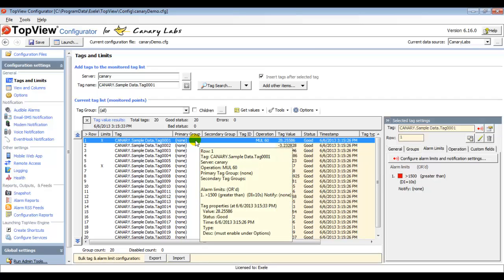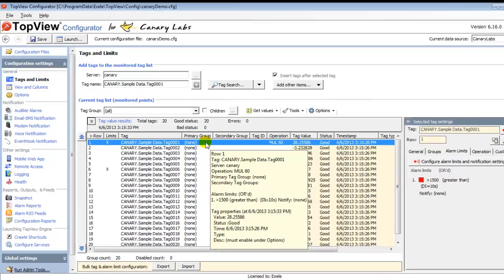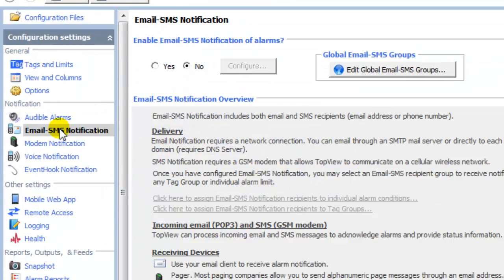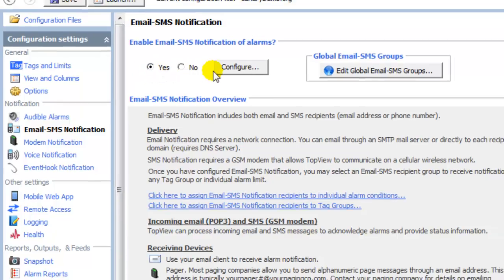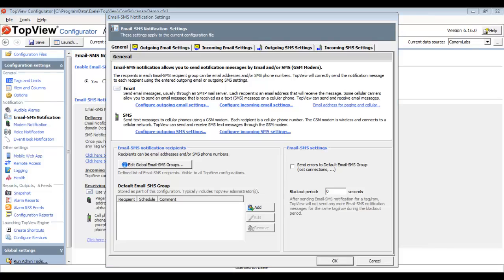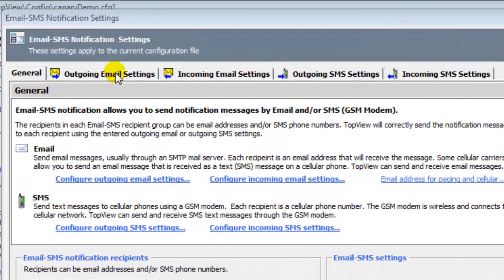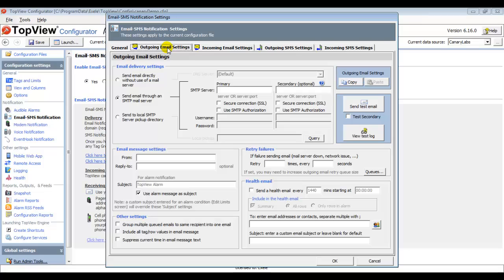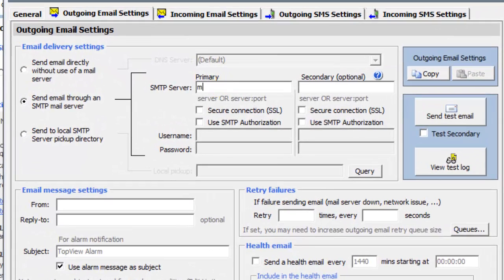I would like to send an email notification when my first alarm condition — the flow value greater than 1500 for 10 seconds — occurs. First, I need to configure the outgoing email settings. I click Email SMS Notification, choose Yes to Enable, and then click the Configure button. Using this screen, I can configure outgoing and incoming email settings using a mail server, as well as outgoing and incoming SMS using a GSM cellular modem. I will send email notification messages using my SMTP mail server, so I need to enter my mail server name. If your mail server requires authorization or SSL, you can enter this information along with the server name. Next, I will enter a from address for the outgoing email messages.